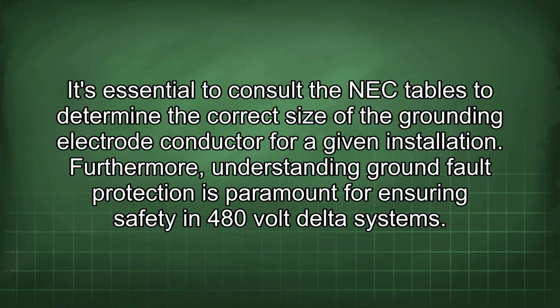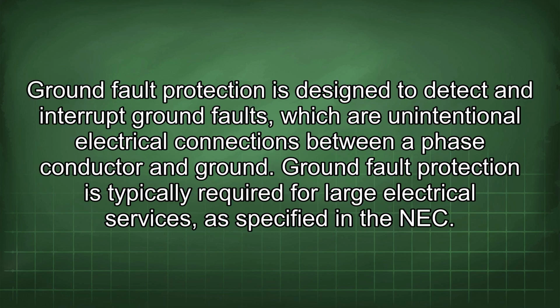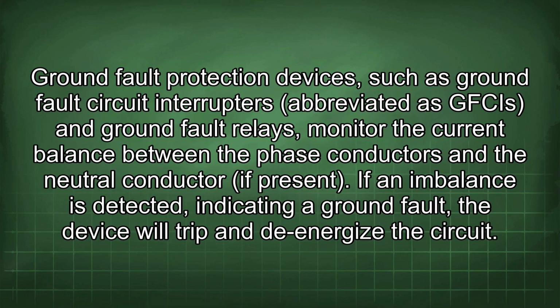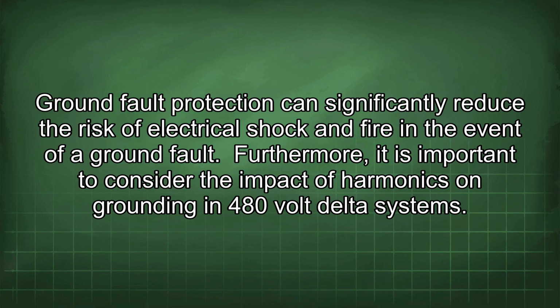installation. Furthermore, understanding ground fault protection is paramount for ensuring safety in 480-volt delta systems. Ground fault protection is designed to detect and interrupt ground faults, which are unintentional electrical connections between a phase conductor and ground. Ground fault protection is typically required for large electrical services, as specified in the NEC. Ground fault protection devices, such as ground fault circuit interrupters, abbreviated as GFCIs, and ground fault relays, monitor the current balance between the phase conductors and the neutral conductor if present. If an imbalance is detected, indicating a ground fault, the device will trip and de-energize the circuit. Ground fault protection can significantly reduce the risk of electrical shock and fire in the event of a ground fault.